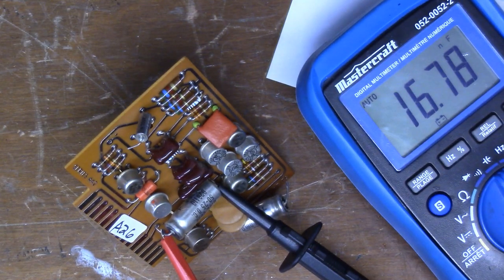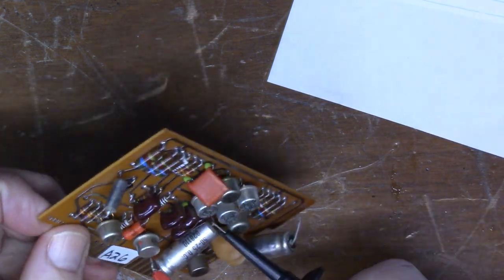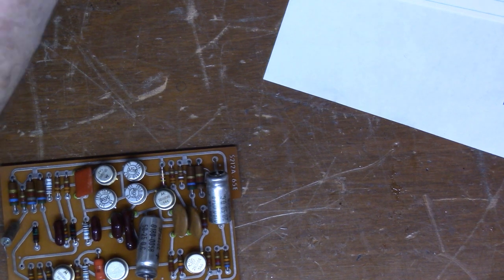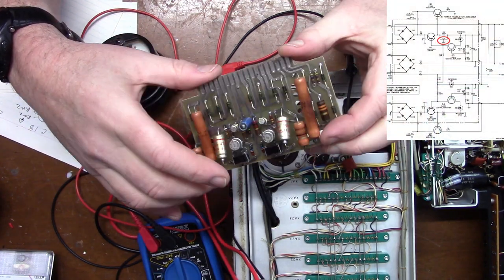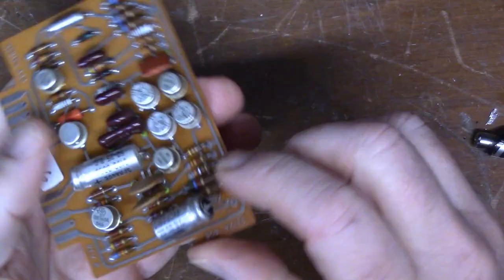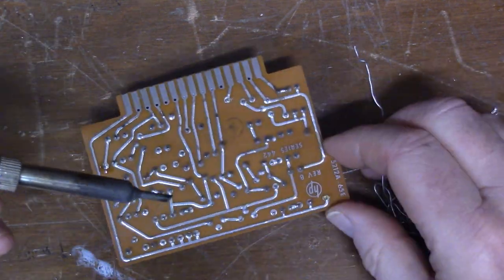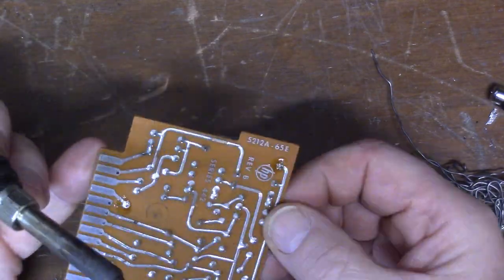As it turns out that wasn't it for the cards. As my high voltage bench was already set up for reforming caps and I still had one of the big caps to go through, I took the opportunity to lift one lead of each of the electrolytic caps on the cards so I could test the capacitance out of circuit. And if required give each a quick reformat. Unfortunately all the electrolytic caps tested high and they were all out of tolerance. I even discovered this on the A1 power supply assembly. What I discovered was this one here was 47 microfarads, so obviously whoever mucked with this before didn't have the correct capacitor to put back in. And of course I don't have a 10 microfarad axial capacitor hanging around in my inventory. As it turns out all I did have in my inventory were the unobtainium wet tantalum caps, all of which of course tested fine. So in for a penny in for a pound, I decided I might as well replace all the electrolytic capacitors on the boards.